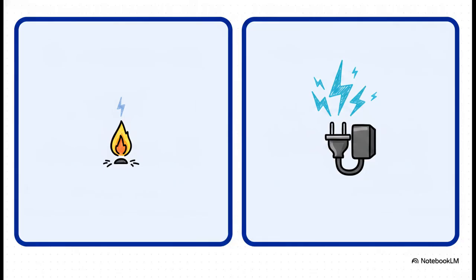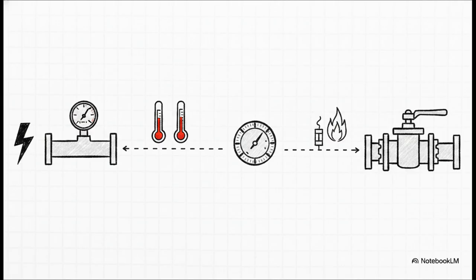Now, the power running through this loop obviously has to come from somewhere. And it's fascinating, older systems use a standing pilot light generating just a tiny millivolt of power. That is less than 1 volt controlling a massive heater. Modern electronic units, though, use a transformer bringing in 24 volts. But regardless of the source, this is the exact electrical current we're going to be tracking as our prime suspect. And this builds our ultimate troubleshooting map.